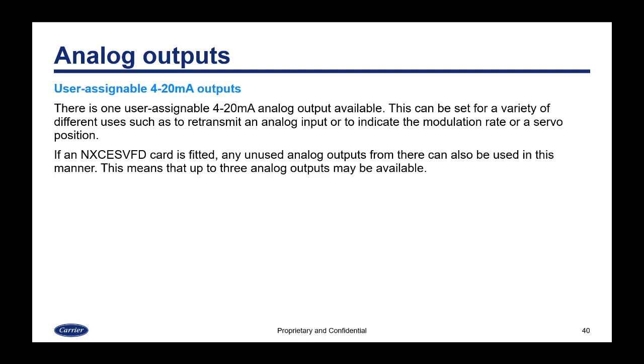And if an NXD or an NXCES VFD card is fitted, that's the VFD add-on card, any unused analog outputs from there can also be used in this manner as well. So if you only have one VFD, your second VFD channel that's unused, you can use the analog output to assign a temperature retransmit, a servo position, or whatever you would need to use it for.